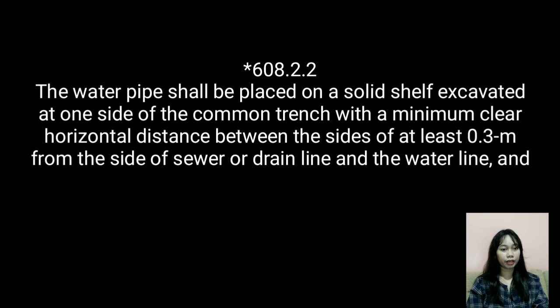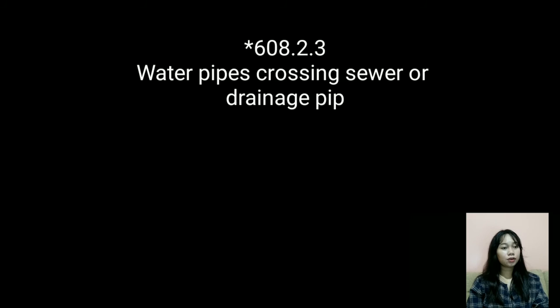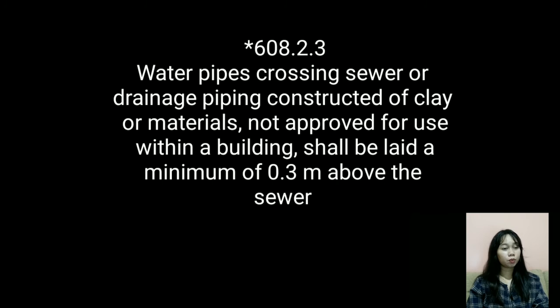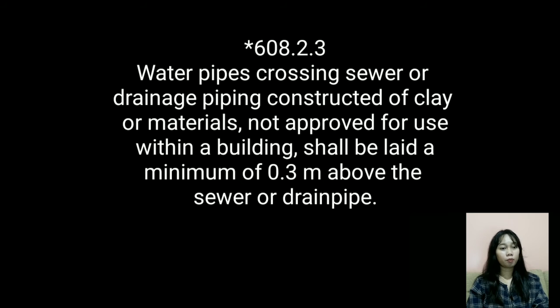Section 608.2.2: The water pipe shall be placed on a solid shelf excavated at one side of the common trench with a clear horizontal distance of at least 0.3 meter from the side of the sewer or drain line to the water line. Section 608.2.3: Water pipe crossing sewer or drainage piping constructed of clay or materials not approved for use within a building shall be laid a minimum of 0.3 meter above the sewer or drain pipe.